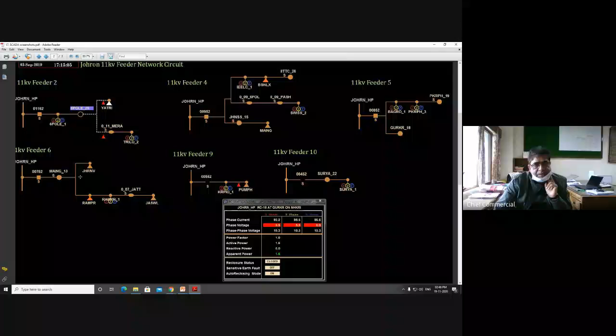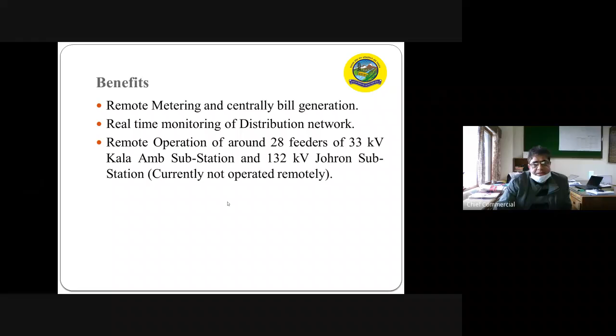This SCADA system, as everybody might already know, is working throughout India through the SLDCs, the state load despatch centres. There is a complete SCADA system for 66 kV and above available, but now under this smart grid project, all 33 kV substations and below are being covered by the SCADA system. So this is remote metering, central visualization, and remote operations. Currently we are not doing it at 132 kV substations because they are connected to the central SLDC, so we are not operating them under this smart grid project. So thank you very much.